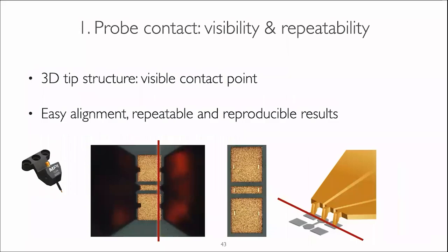With the new generation of wafer probes, as an example shown here, where we have a 3D structure of the contact tips, the point of contact is as visible as for DC measurements. So you can clearly see the point of electrical contact under the microscope, and you can locate the probe at the desired position on the contact pad, and do it any time you want to probe a device under test or touch down on the calibration substrate. So alignment of the probe is very easy, and thus repeatable and reproducible results are very easy to achieve. In fact, for the new generation of probes, you don't even need to use the alignment structures.